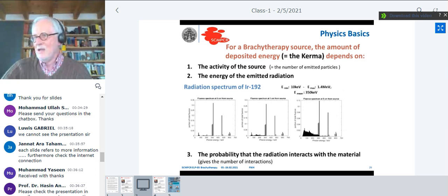The energy of the emitted radiation for iridium, for instance, looks like this. It's a spectrum of radiation which ranges from something like 10 keV to over 1 MeV, with a mean energy of 350 keV. What you see here is the spectrum of iridium at the surface of the source - this is the primary spectrum, which is a line spectrum. Then the spectrum becomes broader and changes with depth in matter.